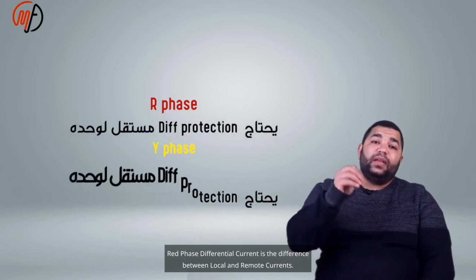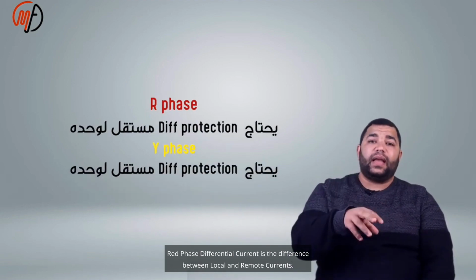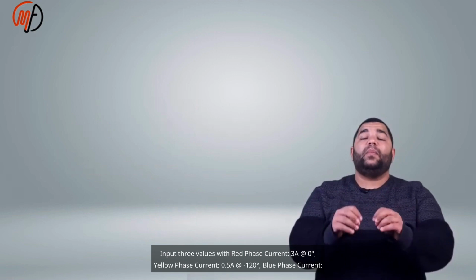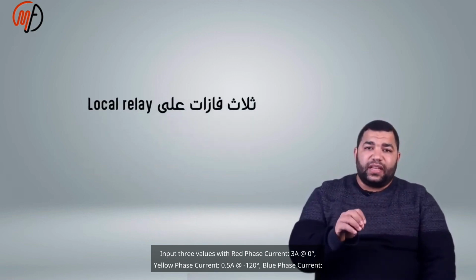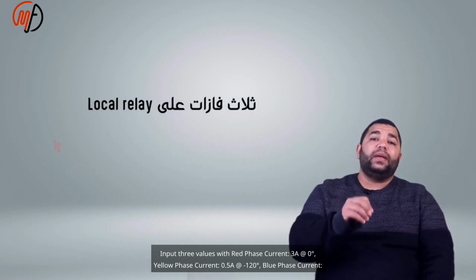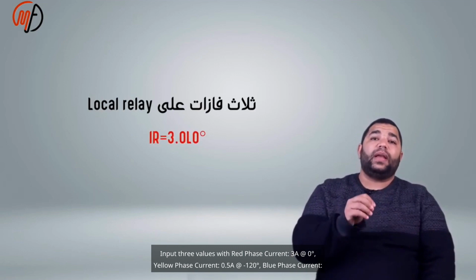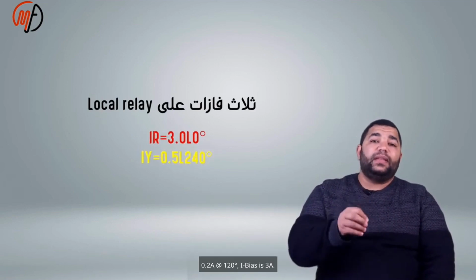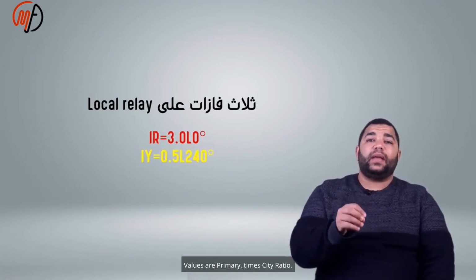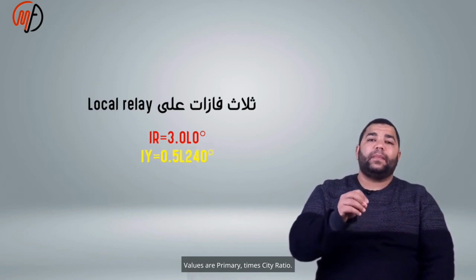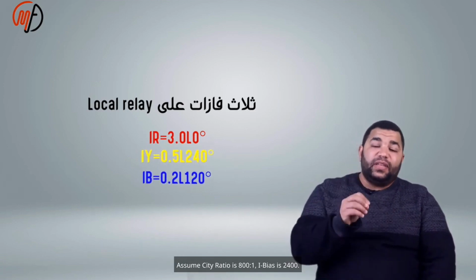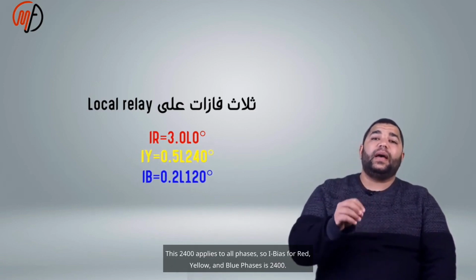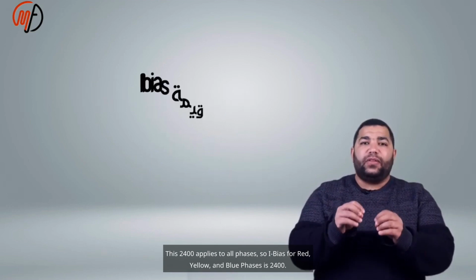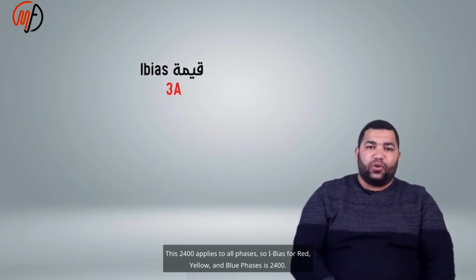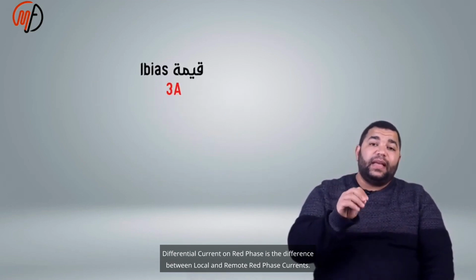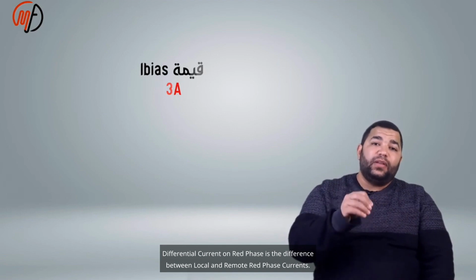Red phase differential current is the difference between local and remote currents. Input 3 values with red phase current 3A at 0 degree, yellow phase current 0.5A at -120 degree, and blue phase current 0.2A at 120 degree. I bias is 3A. Values are primary times CT ratio. Assume the CT ratio is 800:1. I bias is 2400. This 2400 applies to all phases, so I bias for red, yellow, and blue phases is 2400.